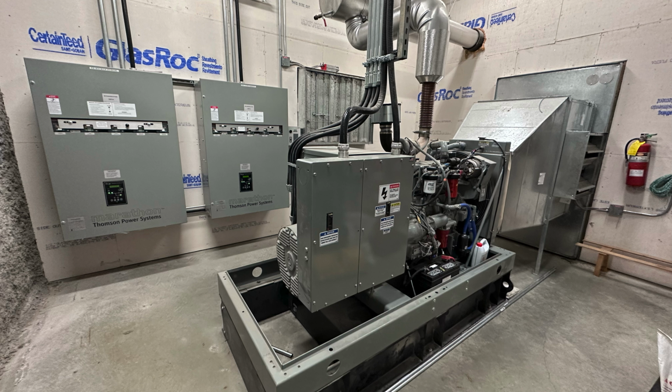This gets done at every generator in the school district, and it has to be done once a year, for 2 hours. On a brand new install, for the first time the load testing is ever done on the generator, it's the same idea, but it has to be done for 4 hours instead.